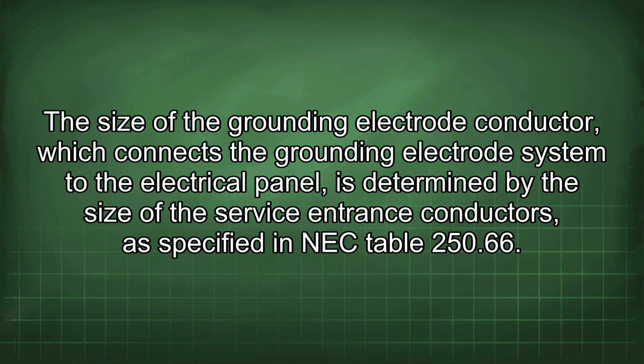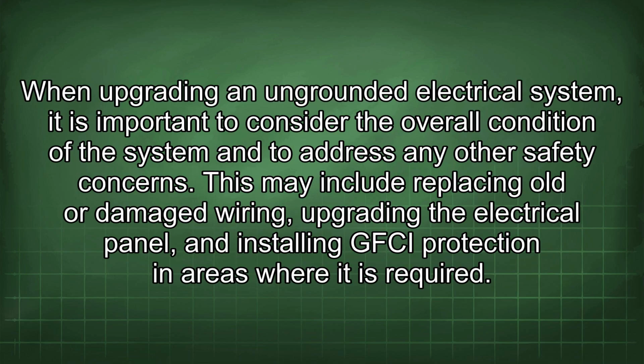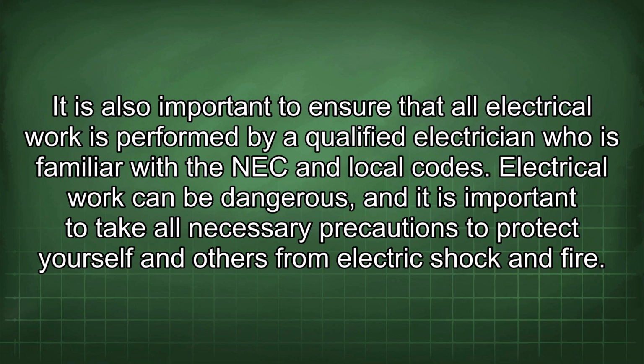The size of the grounding electrode conductor, which connects the grounding electrode system to the electrical panel, is determined by the size of the service entrance conductors as specified in NEC Table 250.66. When upgrading an ungrounded electrical system, it is important to consider the overall condition of the system and to address any other safety concerns. This may include replacing old or damaged wiring, upgrading the electrical panel, and installing GFCI protection in areas where it is required. It is also important to ensure that all electrical work is performed by a qualified electrician who is familiar with the NEC and local codes.